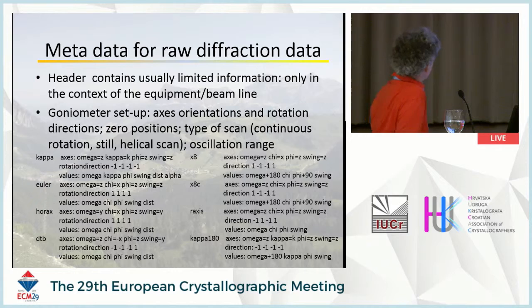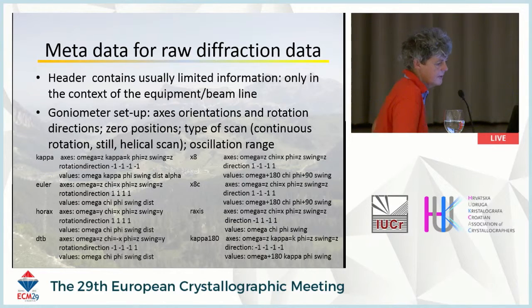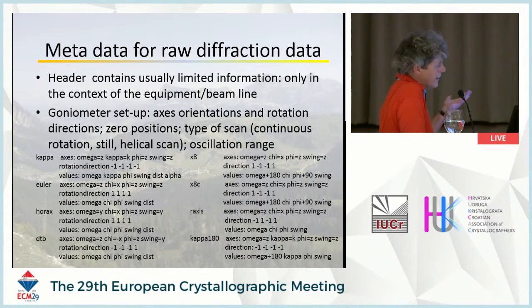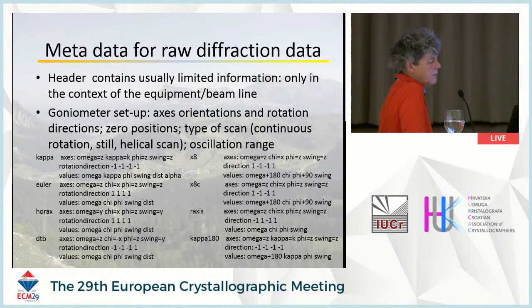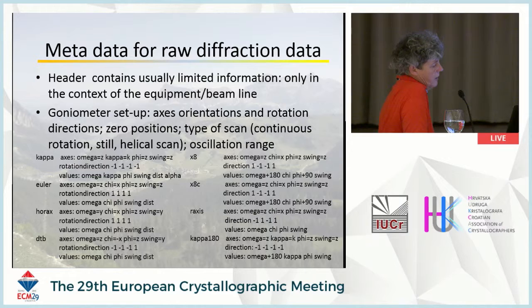So what metadata do we need to store raw diffraction data? I find that headers usually contain very limited information, and when they do it's in the context of the specific beamline equipment. For the goniometer, we should know the axis orientations in lab space, rotation directions, zero positions — which matter when you have multiple goniometer axes — and what type of scan it was: continuous, still images, helical, etc., and the oscillation range.